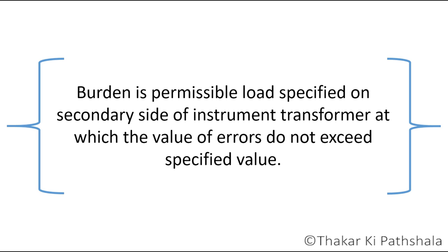Burden, it is very important because in practice, nominal ratio of current transformer, which is rated primary winding current to rated secondary winding current, does not remain constant due to various kinds of reasons like power factor on secondary side, core loss component, secondary side current, etc. So, burden is permissible load specified on secondary side of instrument transformer, at which the value of error does not exceed specified value.